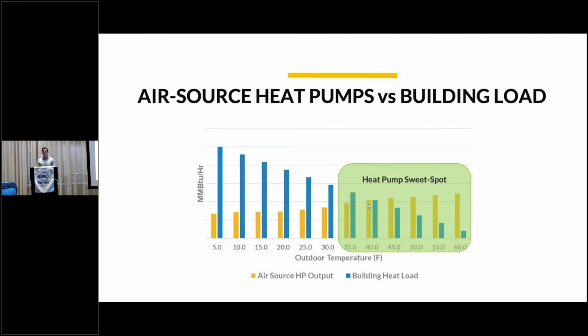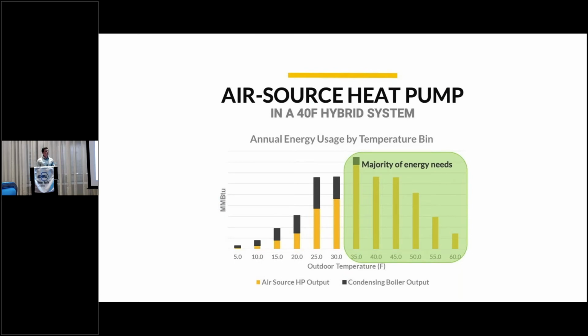But then if you look at the actual building's energy usage in these temperature bin counts, you see something really interesting, where if you have that same heat pump sized for 40 degrees Fahrenheit, you're actually able to cover a majority of your building's energy usage from that heat pump. Even though it's derating, you're still able to cover it. But what you have to do is combine your heat pump with another system to make up for that derating. And so we looked at sizing it in conjunction with a condensing boiler system. As our heat pump derates, our condensing boiler kicks on to cover the remaining heating load.